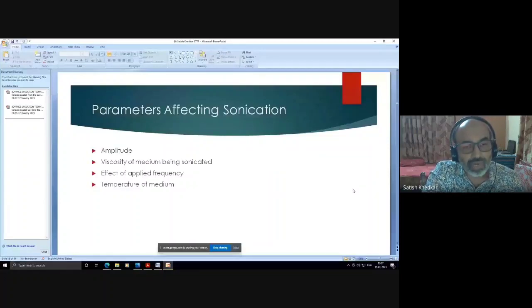Now, the second factor affecting the process of sonication is the viscosity of the medium being sonicated. As I have told you earlier, viscosity is the cause of load on the transducer or the sonication probe, because viscosity restricts the movement of the probe. The probe will not be able to vibrate freely when a highly viscous medium is there. So the viscosity of the medium will affect the movement of the probe in the liquid being sonicated, and it will be a cause of load on the transducer. So viscosity is another factor.